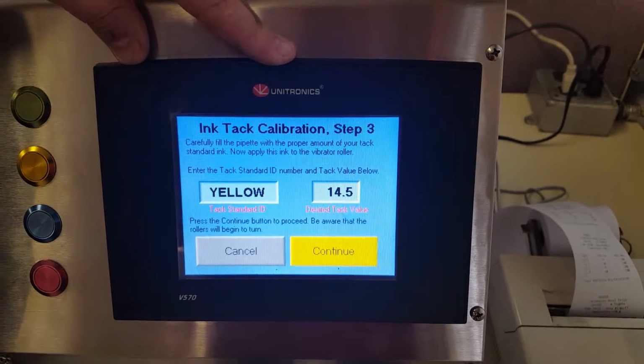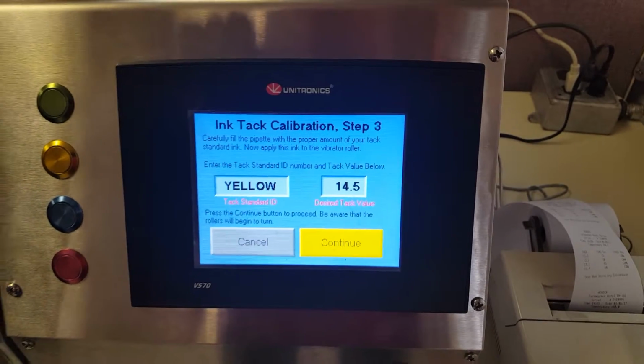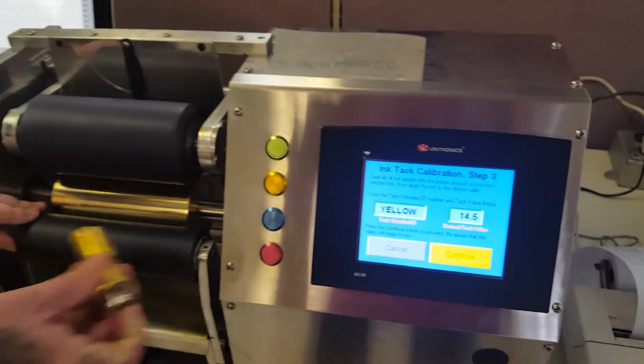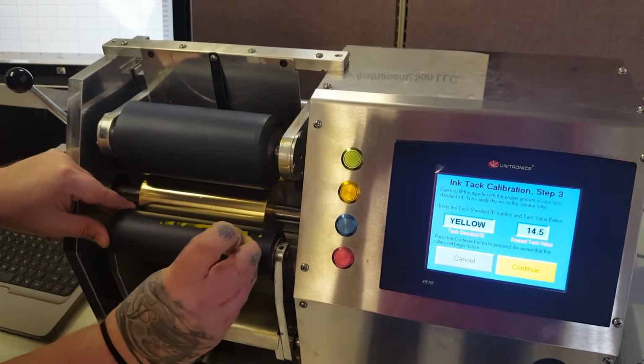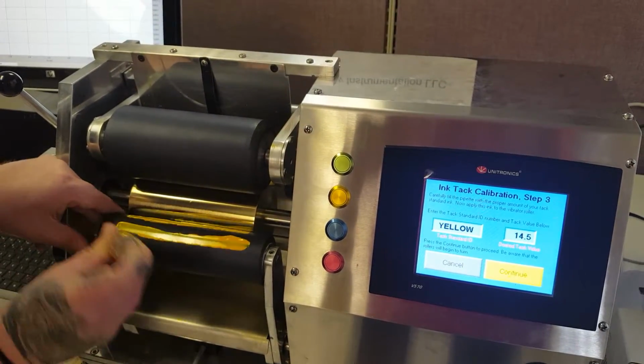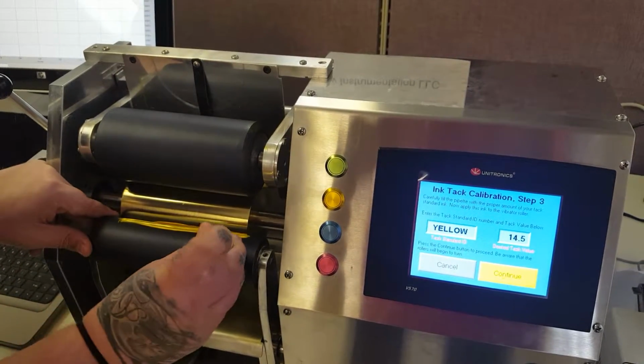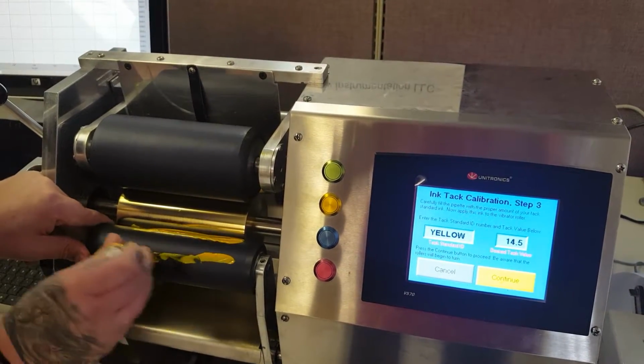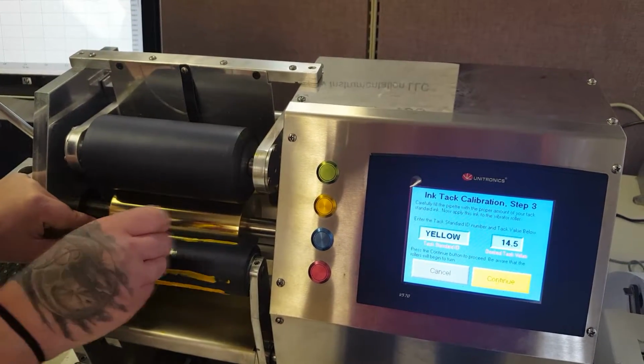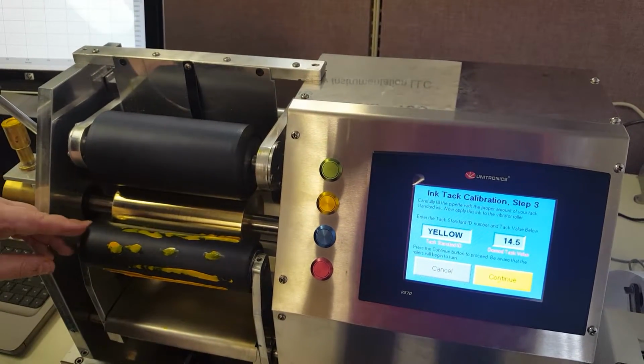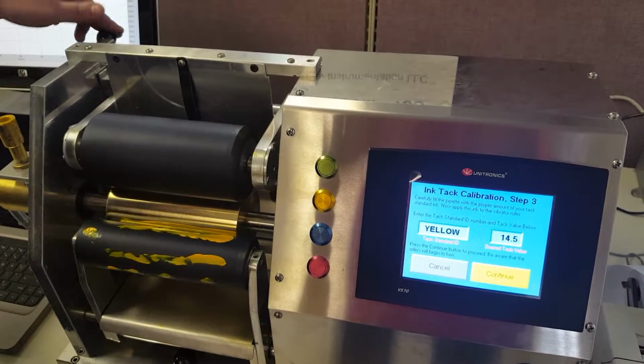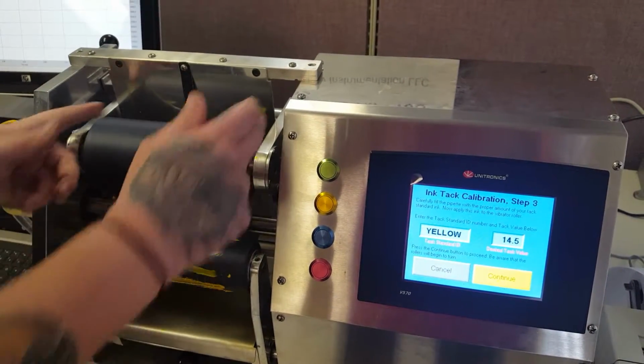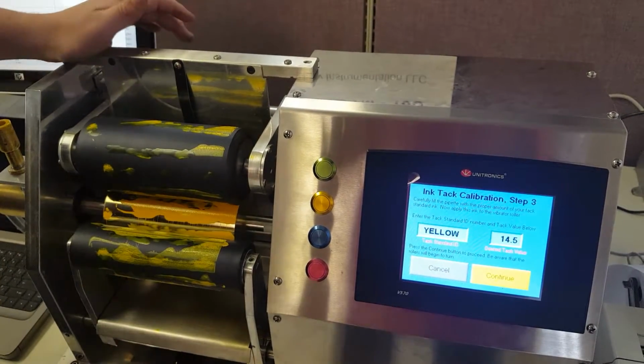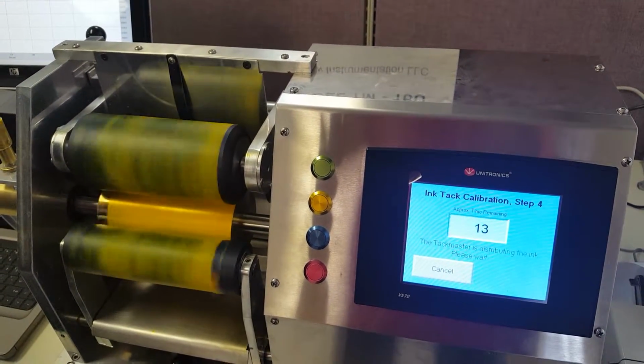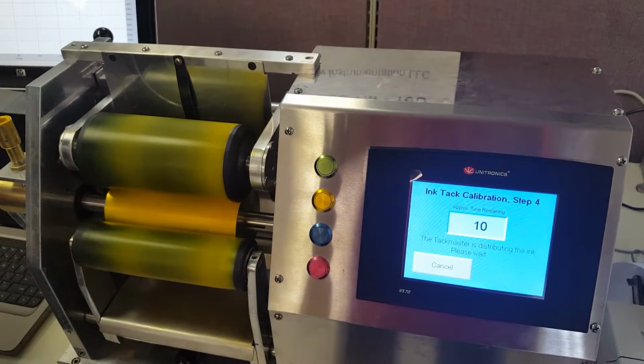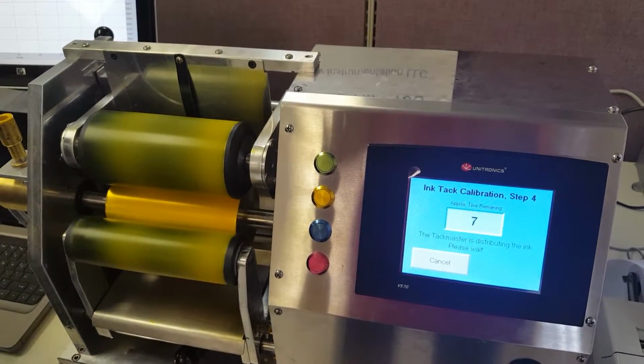So now, before I hit that continue button, I'm going to apply some ink to this machine, just like I would do if I was running an automatic or manual test. This is our tack rated yellow here, and we use this for calibrating all of our instruments for the most part. Nothing different about this portion other than the fact that the PLC does all the work. I'll just give that a little turn, and now I will hit the continue button. Now this is going to distribute the ink for 15 seconds, which is the parameter, again, that I had set up in our test setup area.